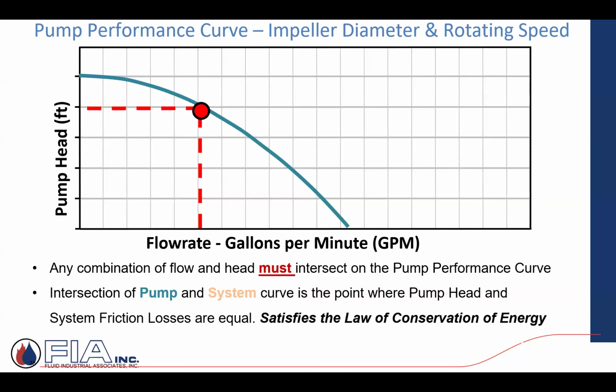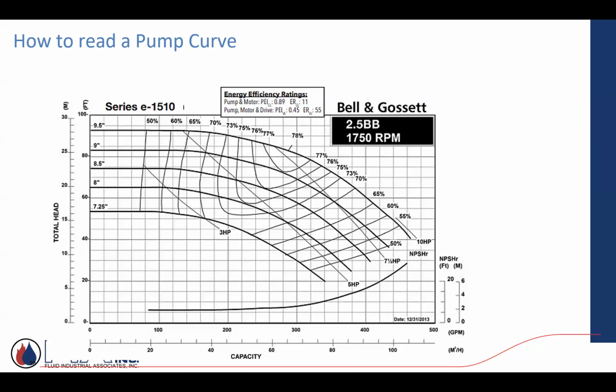Pump curves, fundamentals. We kind of started talking about this. But any kind of flow and head must intersect the pump curve. When the pump turns on, it's going to operate somewhere on its curve. Where that pump curve and the system curve intersect, that's where, I guess you could say, it satisfies the law of conservation of energy. Energy in, energy out. The pump doesn't know what you selected. It's just going to turn on and run and pump as many gallons a minute as it can relative to the resistance the system offers. We want those two ideally to intersect, that system performance curve with the pump that we designed, specified, and selected. That would be ideal. So when you look at a pump curve, how do you read it?